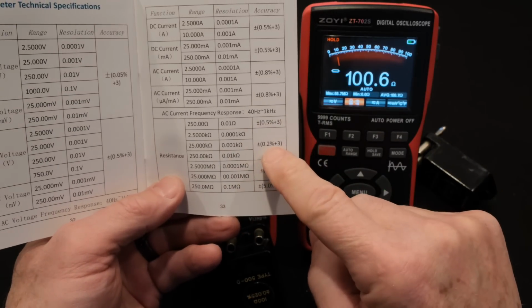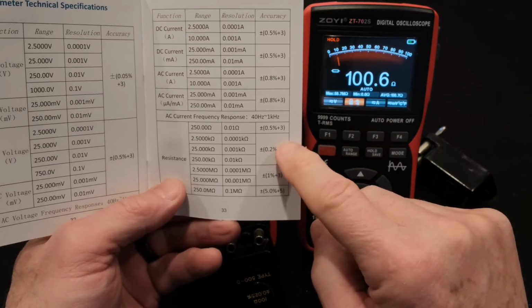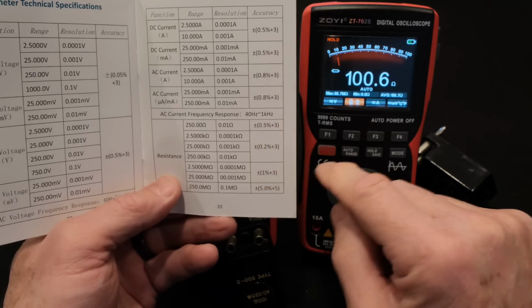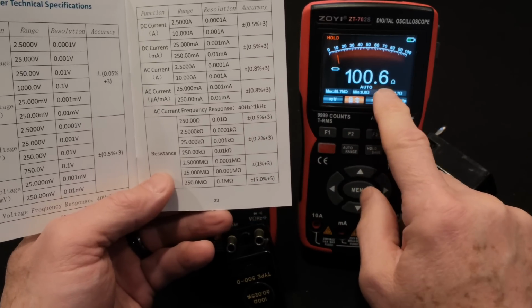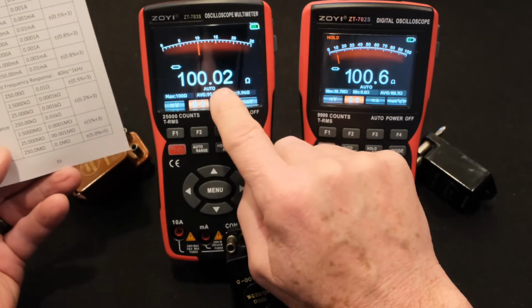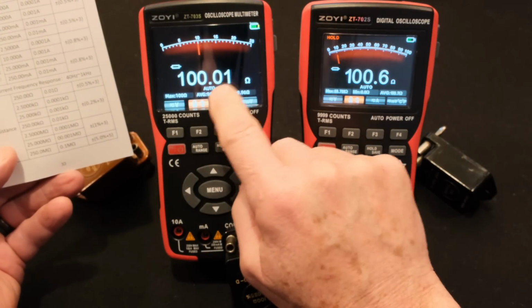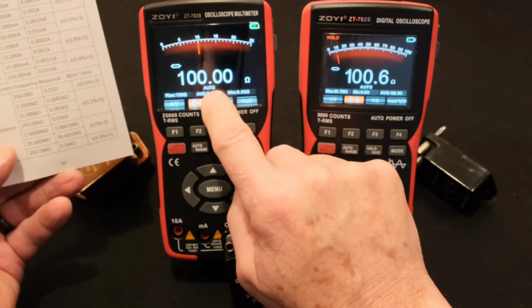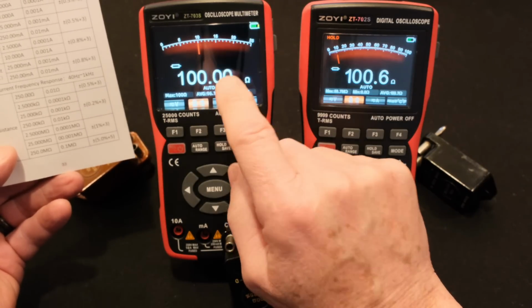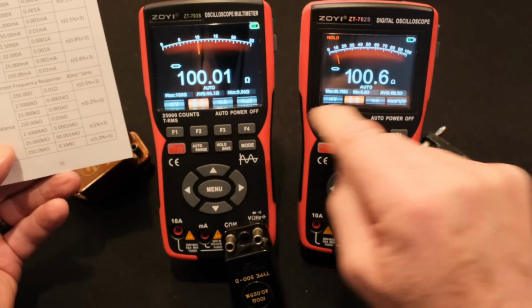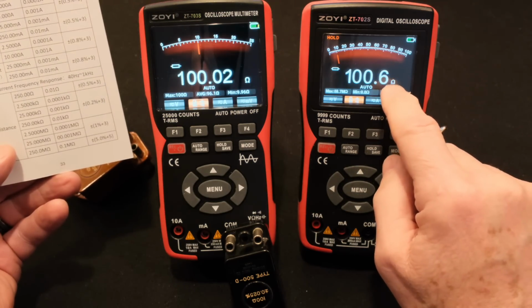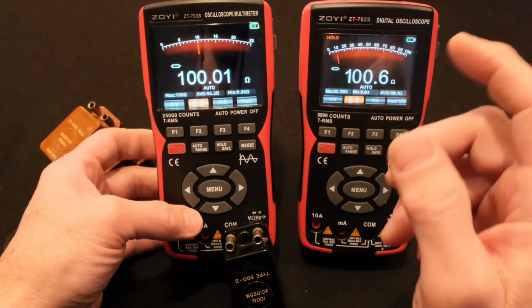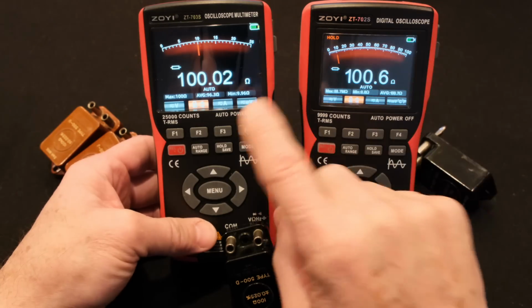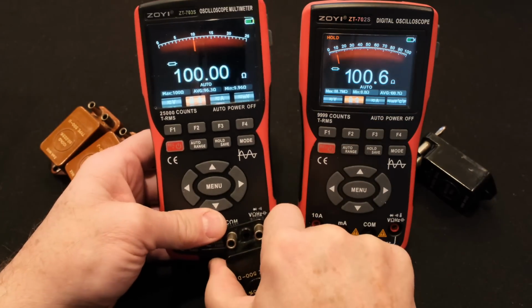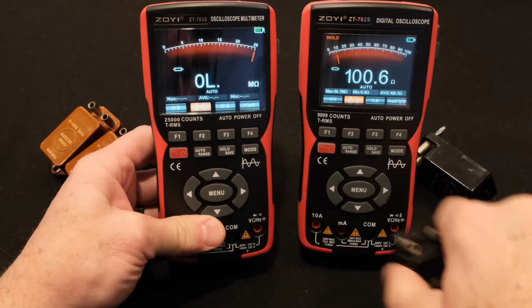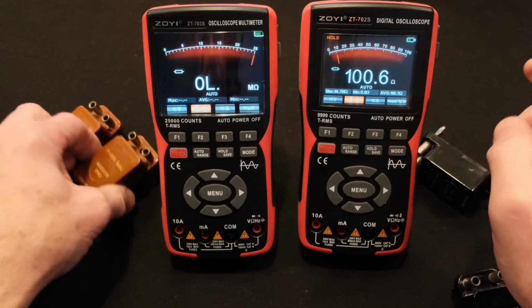So then we go to 0.2%, and the last digit is at 0.3%. So in a case like this, in low ohms, even on this one, the last digit is 0.0, so it's not as bad. The digit right after the decimal point has good tolerance, good accuracy, where on the lower count meters, they don't. All right, now that we've got that covered, we can see we're totally in range. This one's almost perfectly dead on if that's a perfect 100 ohm resistor, right? Okay, so let's go to the next one.